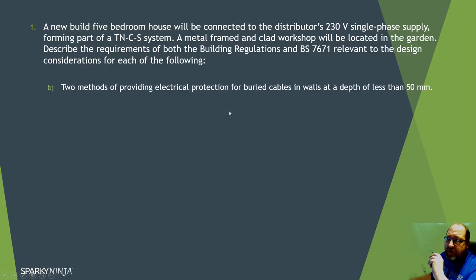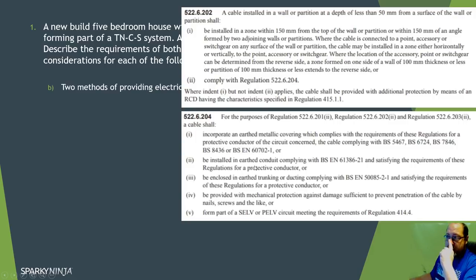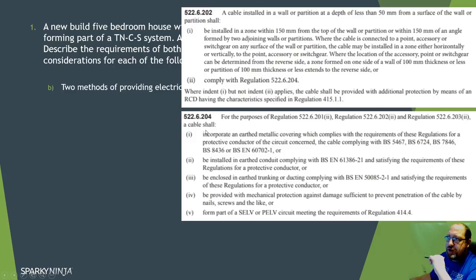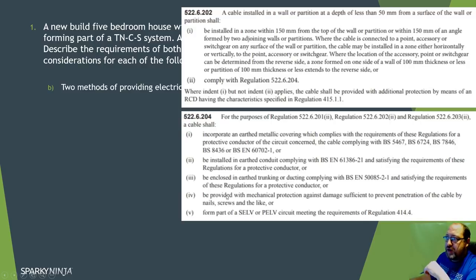For two methods of providing electrical protection for buried cables in the wall, we have regulation 522.6.202 which gives us the zonal directions, and 522.6.204 which gives us the requirements for conduit, metallic covering, earth trunking, and so on. Those are the protective requirements of BS 7671. There's also an illustration of the zonal concept in the building regulations document. So both documents help here - you're looking at things like protecting against mechanical damage.